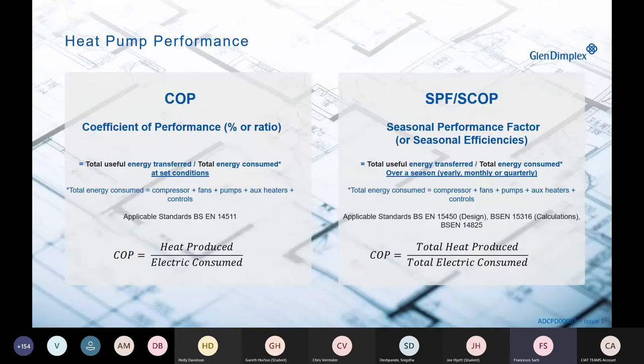The way we measure efficiency of heat pumps is slightly different from standard systems. It's because with one unit of electricity driving the compressor, you can have multiple units of heat delivered to your ambient. The main factors we use are the COP and the SCOP. It's worth mentioning also the SPF, but legislation mainly deals with the SCOP nowadays. So what does it mean?